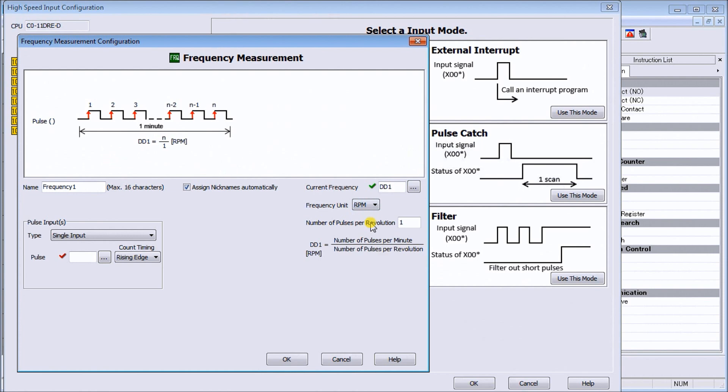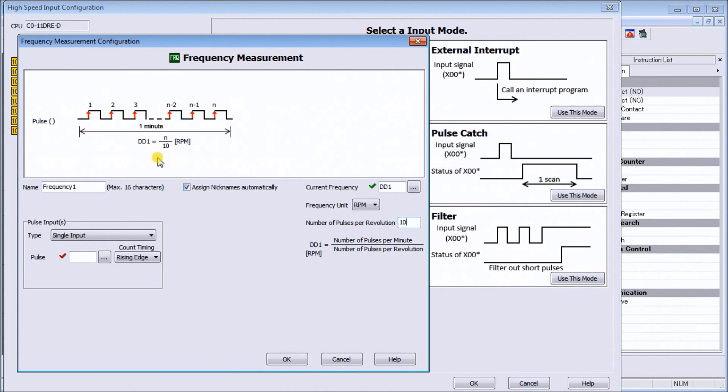Now when we do RPM we have to tell it how many pulses are we getting per 360 degrees. In our case here, off of a drill, we're going to get 10 pulses per 360 degrees. So every 10 pulses is going to do it for the minute and it'll tell me how many RPM I'm going to go.